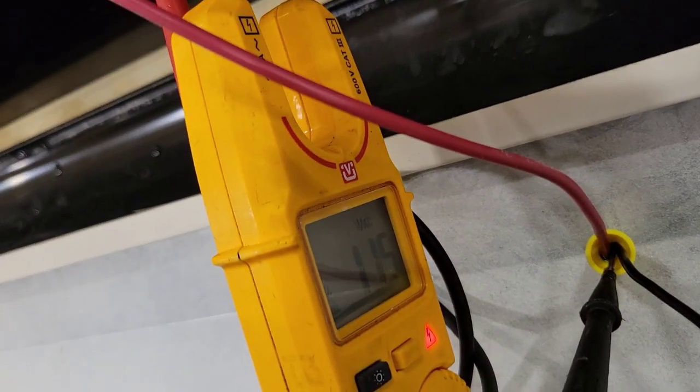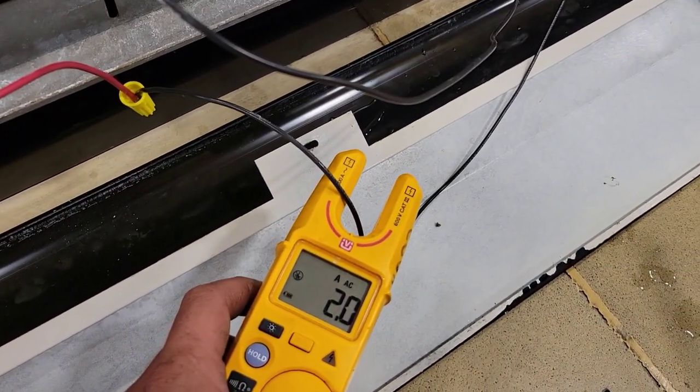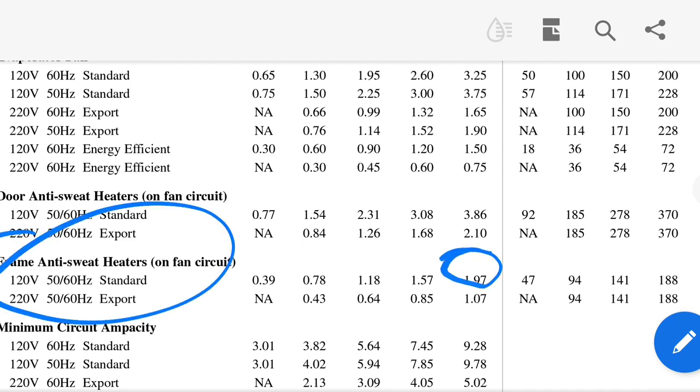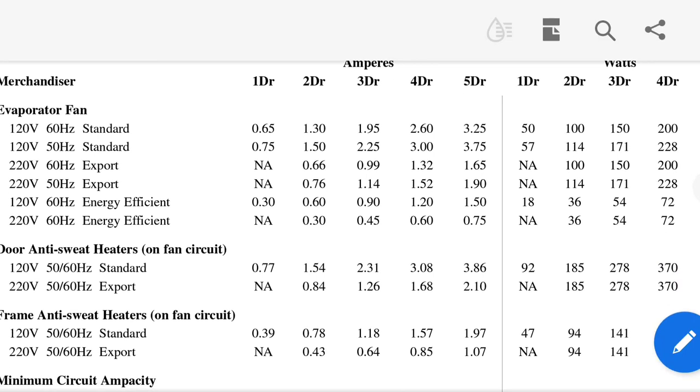We've got voltage. Now let's see if we have any current. Yep, we've got some current going through. Now we're going to see if the heaters are heating. Looking at the RL5 product manual, you can see frame anti-sweat heaters — about 2 amps for the 5-door — so that works out fine.